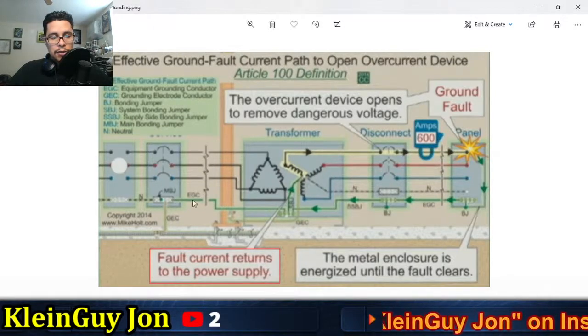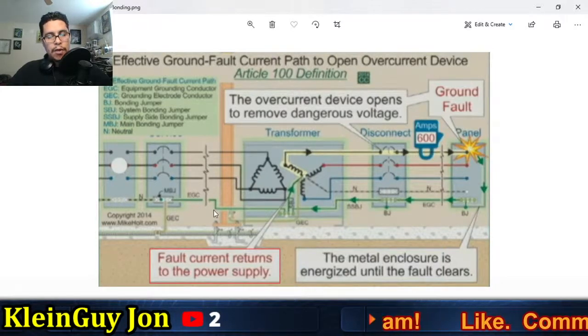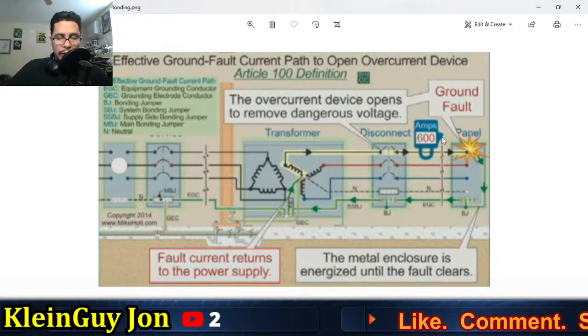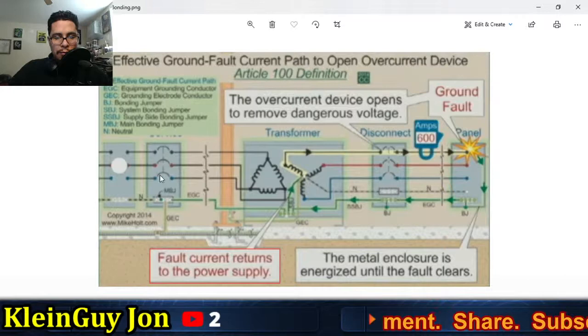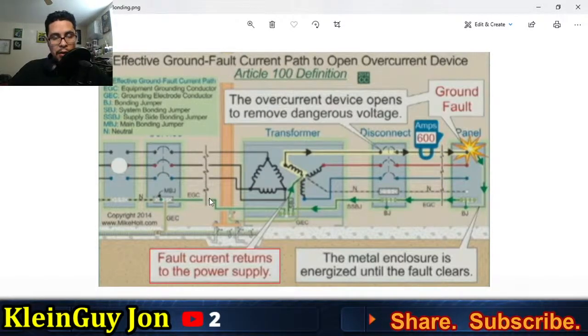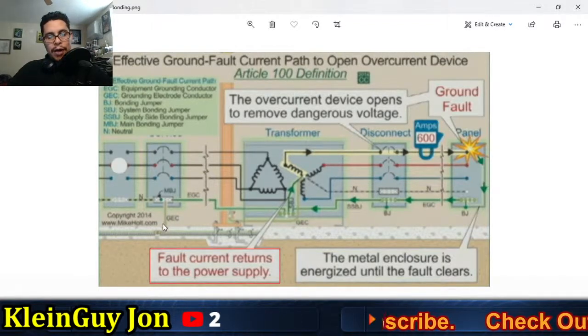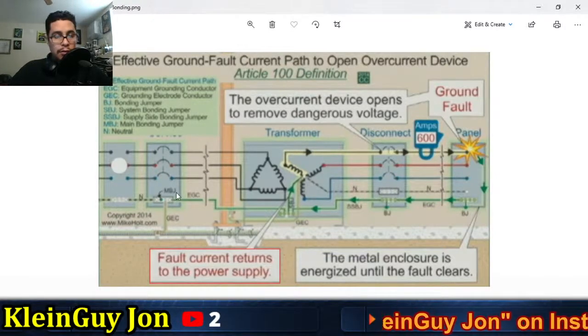No, it's going to go straight to the grounding electrode conductor here at the disconnect, or if you have it bonded to the neutral onto the meter, what happens? You now have objectionable current. Objectionable current is when you have all the electrons going all throughout the building. Actually, I was right. It's going all throughout the building, and it's also going to ground. If you do not have a grounding electrode conductor going to the ground, it will go throughout all the metal around the building, all the building structure. It's going to touch all the metal because it's trying to find its way back to the source.